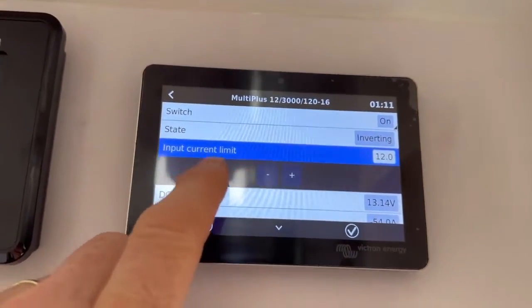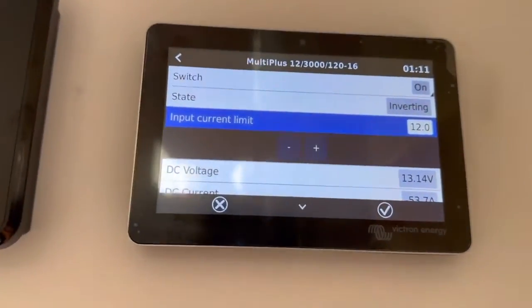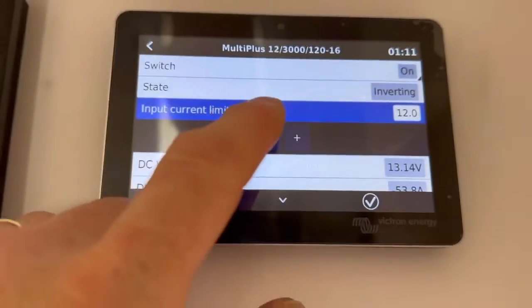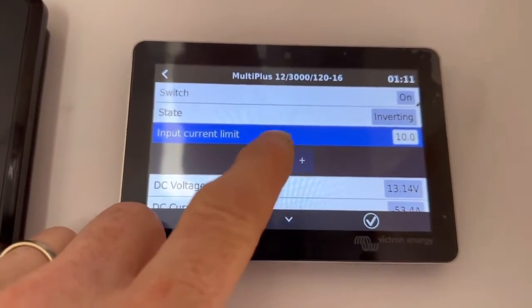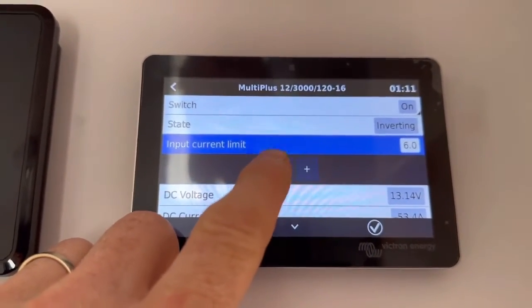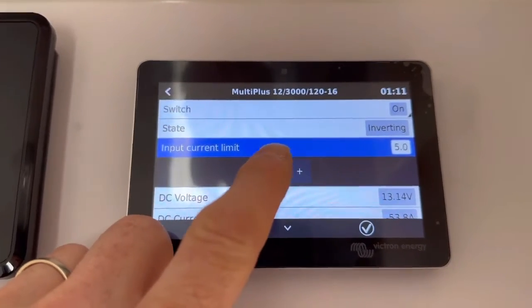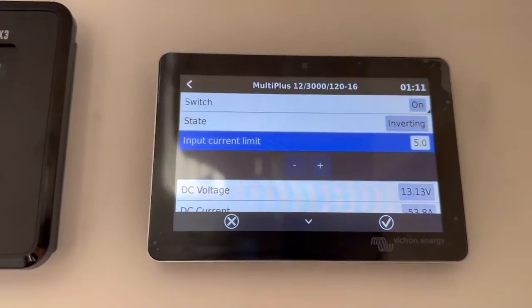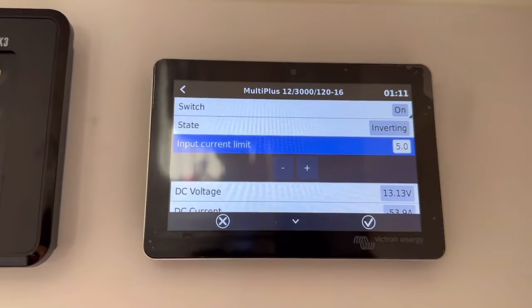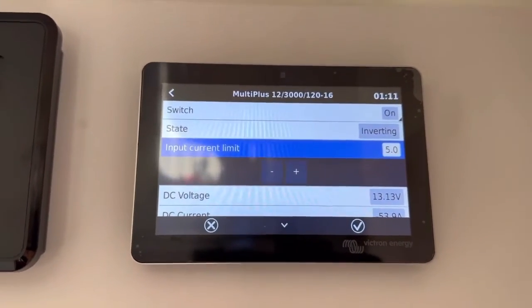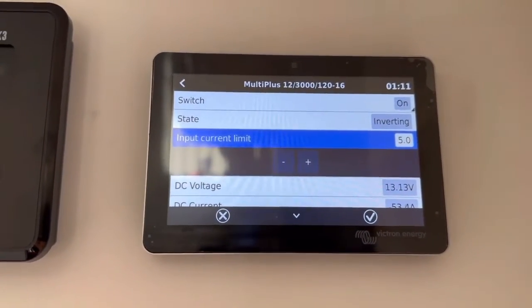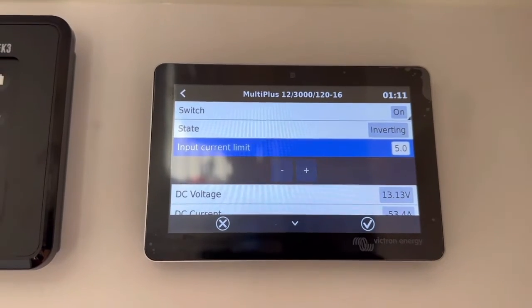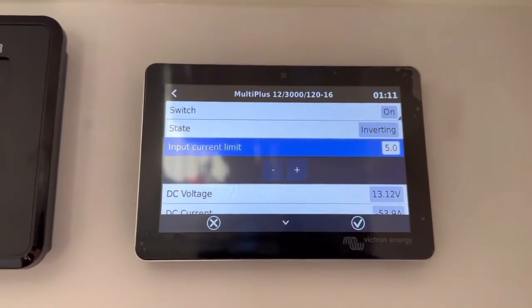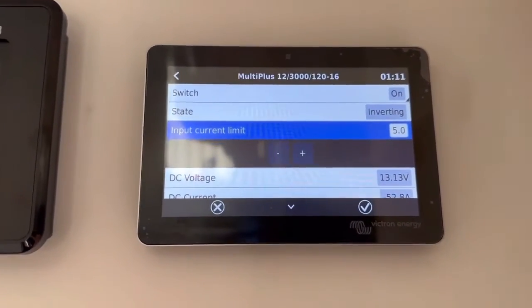We've got input current limit, at the moment it's on 12. We can take that right down, even with a 2 kVA generator, down to around 5, so it's not going to overload your generator. You can have a play with that and find the sweet spot so you're not revving the guts out of your generator while still charging your batteries - you won't charge at as many amps, but still quite efficiently.